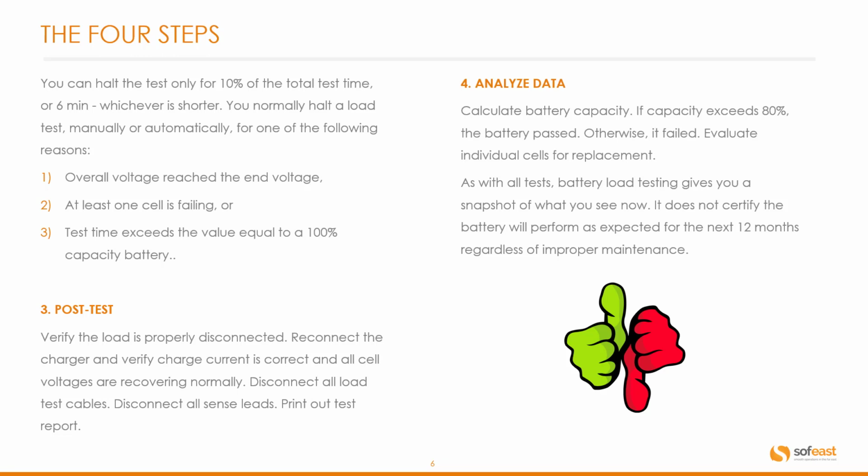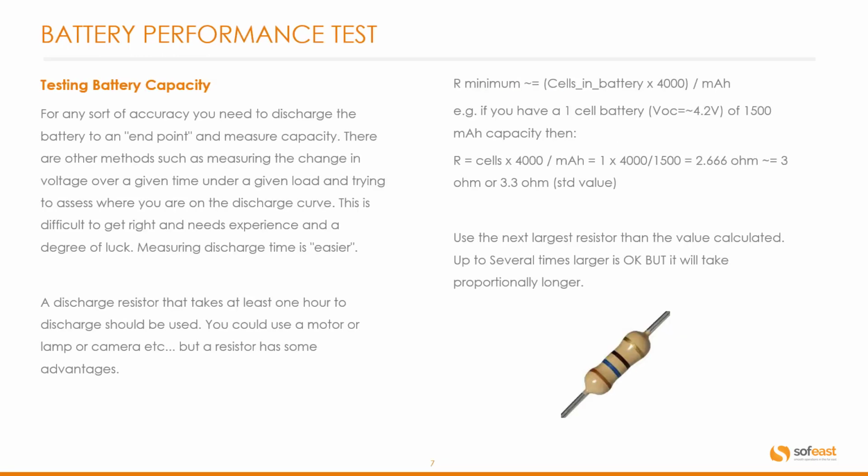As with all tests, battery load testing gives you a snapshot of what you see now. It does not certify the batteries will perform as expected for the next 12 months, regardless of improper maintenance. So battery performance testing. Let's have a look at testing battery capacity.